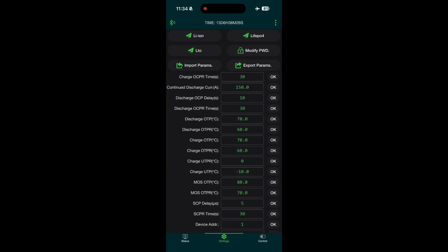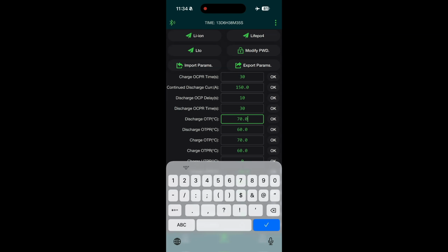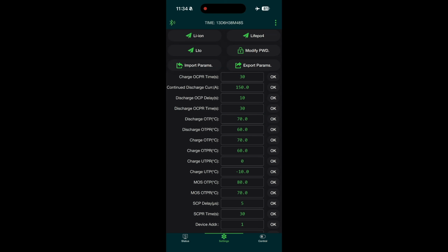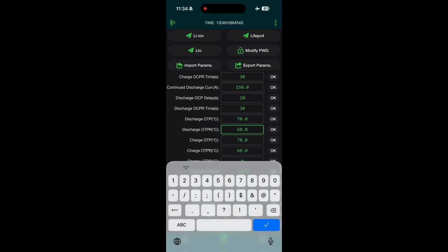Next one down is the temperatures. So where do you want Discharge OTP? This is a temperature. For example, if discharge is set to 70, once it goes over 70 degrees, it's not going to allow the discharge to continue. Next one is the reset value. Same thing, over temperature protect reset for discharge. So again, it'll go up to 70 degrees, and then as soon as it goes under 60 degrees, it will start allowing discharge to happen. So I'm happy to leave those settings there.